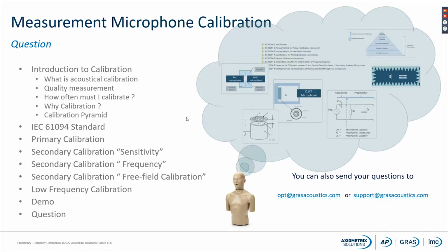Is calibration according to part 8 also possible in a diffuse field instead of a free-field anechoic chamber? Yes, if you use the time selective calibration methods.